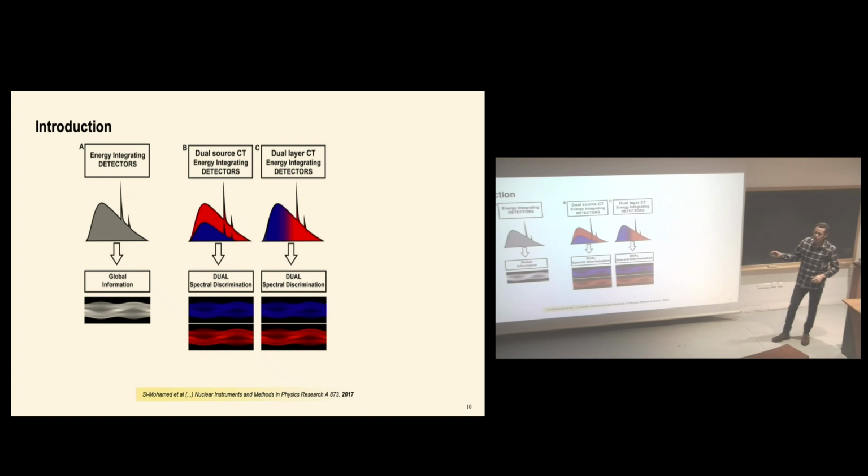Or another constructor provides dual energy not at the acquisition, but at the detection. You will have two layers of detectors with different compounds that discriminate between the low energy and the high energy. We will see that this is the key for a better understanding of the attenuation between the X-rays and the tissue.